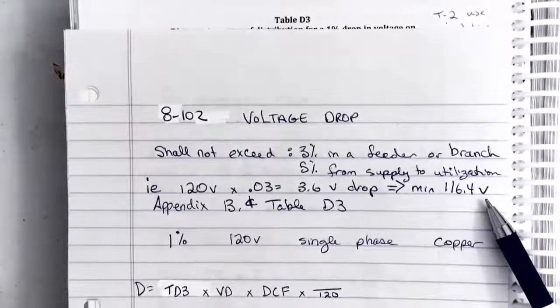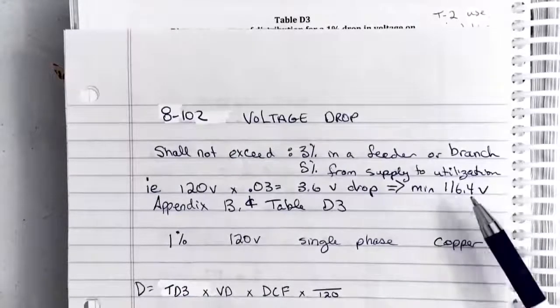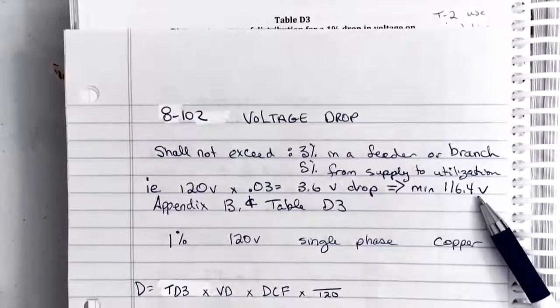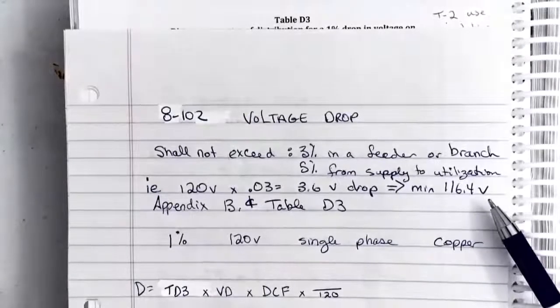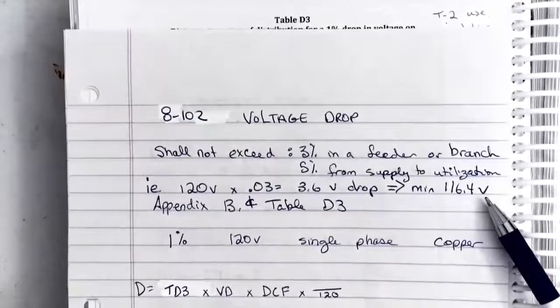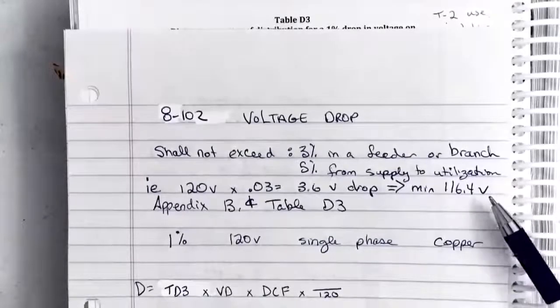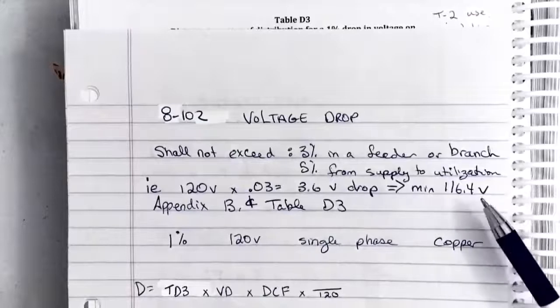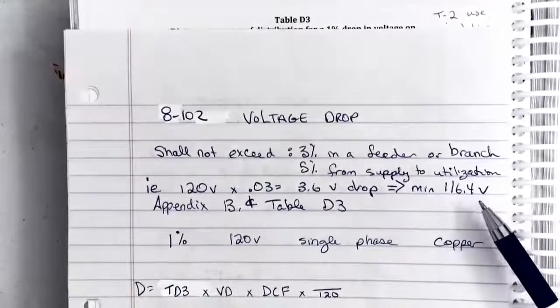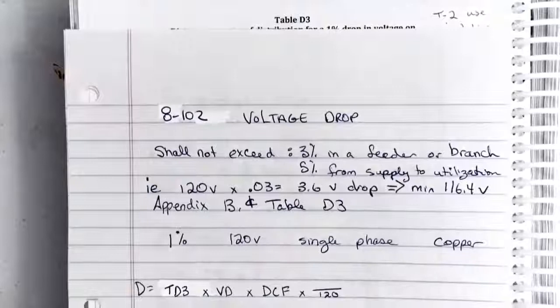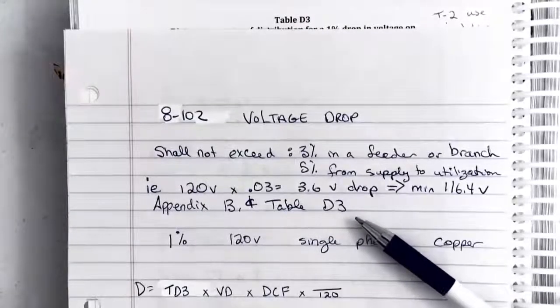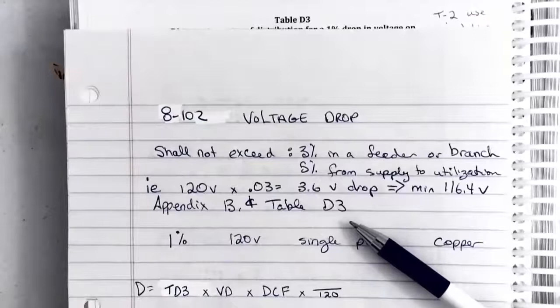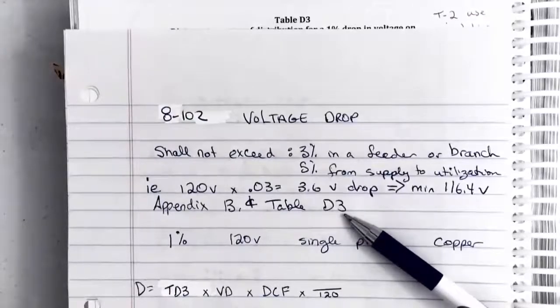This is really important because if this number gets too low we can end up with all kinds of challenges at our load, and the load will not operate correctly. If it's a motor it could overheat and burn out. So we really want to make sure that we don't get a lower voltage than is allowed. Now to help us calculate this out, 8102 sends us to Appendix B and also Table D3.